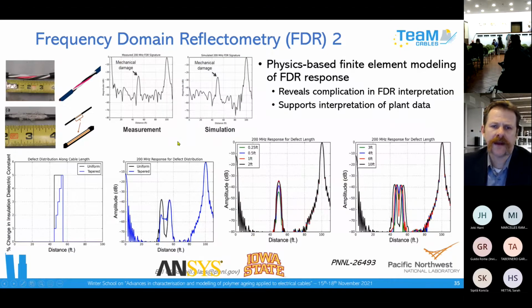We've done some finite element physics-based modeling of FDR responses to understand the effect on the signals. When you get a signal from frequency domain reflectometry and there's a defect, whether that change in impedance is a uniform change or a tapered change affects the shape of your signal. Depending on the frequency you're using, the size of that defect can split your signal into multiple peaks. That understanding is very important as you're trying to make sense of your NDE signals.